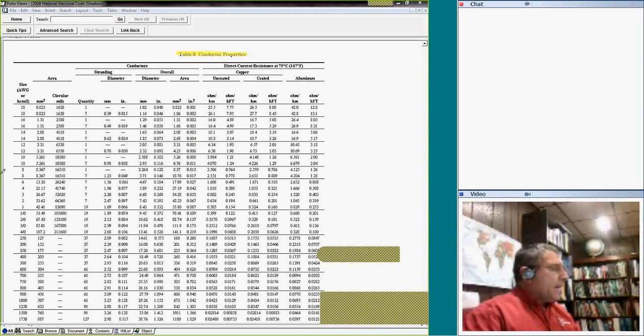And if I ask you, what is the circular mil of number 1/0? No problem. Here's the circular mil, and I hope everybody knows how to find the circular mil. Later on, guys, when you go to your exam, they'll ask you about the resistance for uncoated, unless they tell you it's coated. So if I ask you, what's the resistance per 1,000 feet? Over here, this is ohms per kilofoot, for 1,000 feet. If you go all the way across, for a 1/0 conductor, the resistance for every 1,000 feet of this cable would be 0.122.